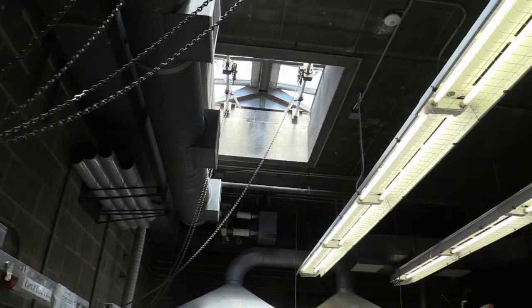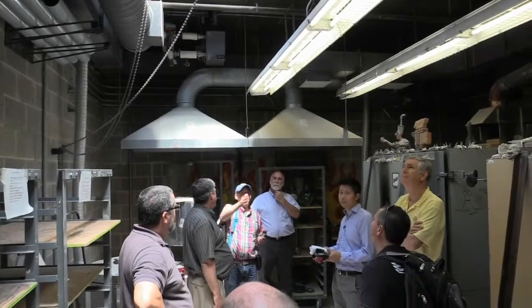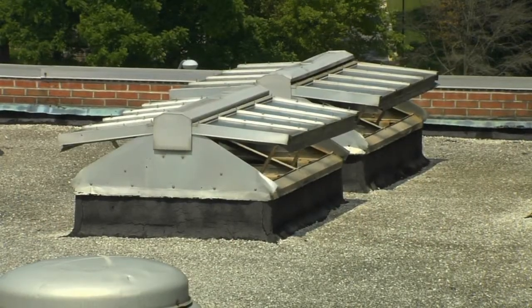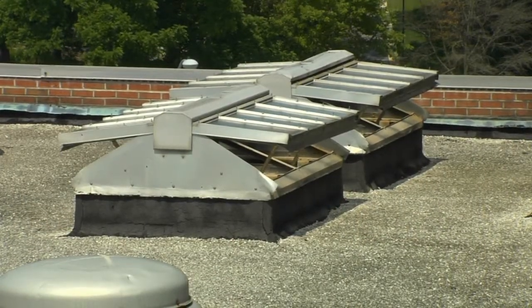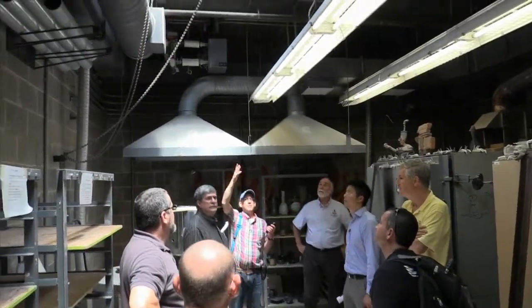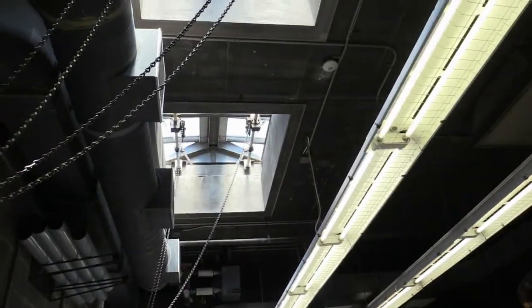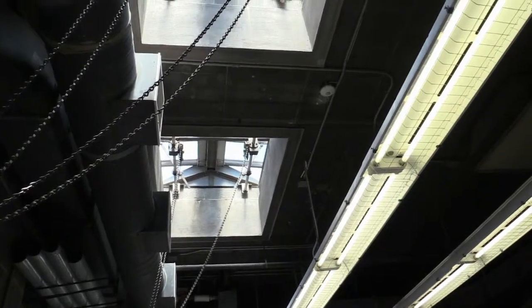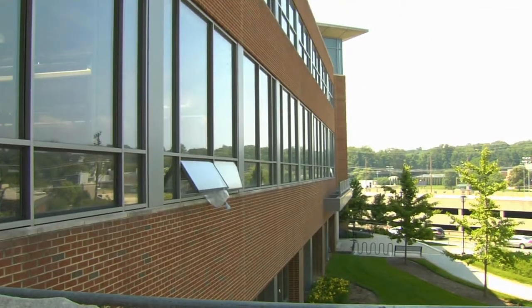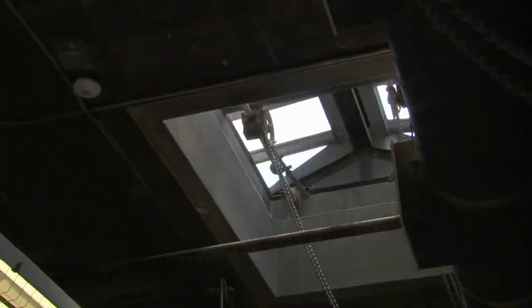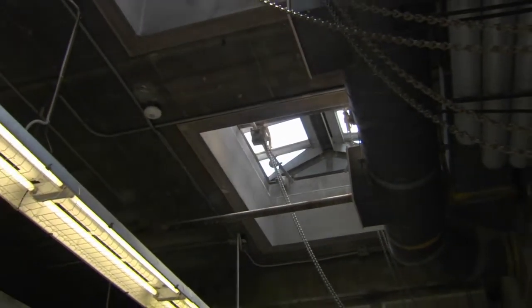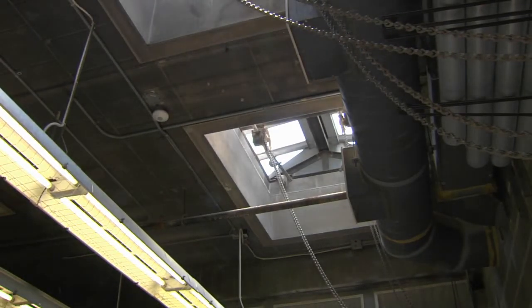Before the upgrades were made, skylights were used to ventilate. These skylights do not appear to be necessary, yet during the walk down we see that they are open. No one knows how long they have been open or what weather conditions this may have exposed the interior of the building to. The same can be said for the operable windows that were noted as being open on the front side of the building, to highlight the importance of paying attention to the building envelope, especially where occupants can impact the envelope integrity by opening windows and doors and then leaving them open.